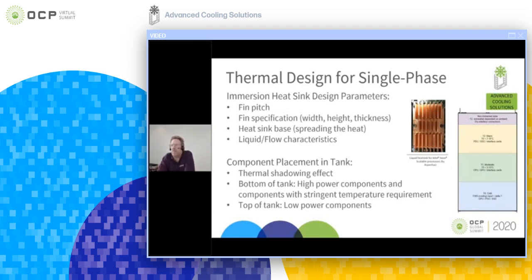You will find with proper analysis that a lot of the thicker fins will allow the energy to spread closer towards the fins extremities, which allows more effective use of surface area of a heatsink in liquid. Whereas an air design heatsink doesn't really utilize the fins that are applied onto a heatsink. Now, another consideration is the heatsink base, which is responsible for spreading the heat, whether it's a vapor chamber or a solid material. The heatsink base must be able to distribute the heat effectively towards the fins. This is also a consideration in air, but much more so with liquid because of the superior characteristics of liquid in absorbing and transporting the heat from one material into the next.